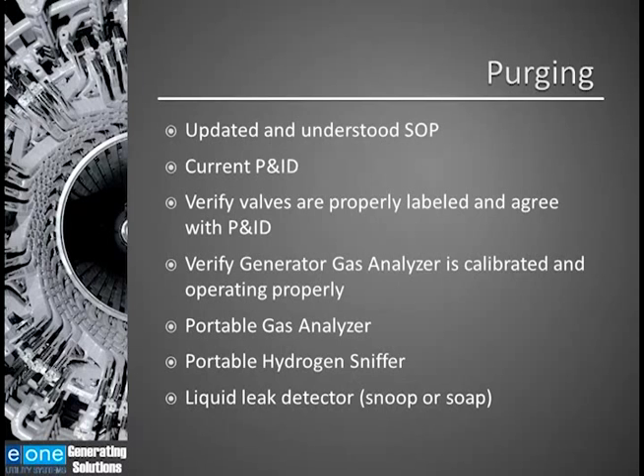You should have a current P&ID. Over years, the piping systems get changed, instrumentation gets added, valving gets changed. You need to make sure that your P&ID is current. You need to verify that the valves are properly labeled and agree with the P&ID. You need to verify that your gas analyzer, whether you're using 1 or 2, is calibrated and operating properly. If you are not using redundant gas analyzers, I would recommend the use of a portable gas analyzer during the purging process as a redundant analyzer.